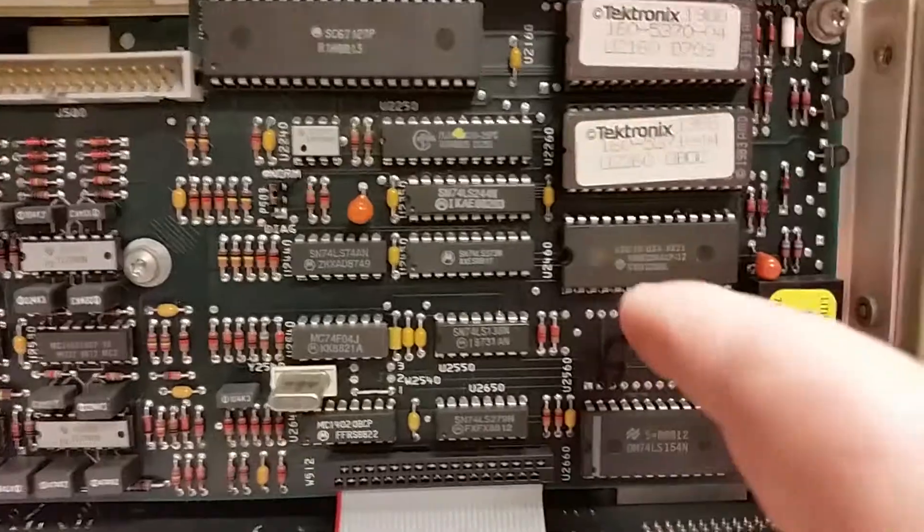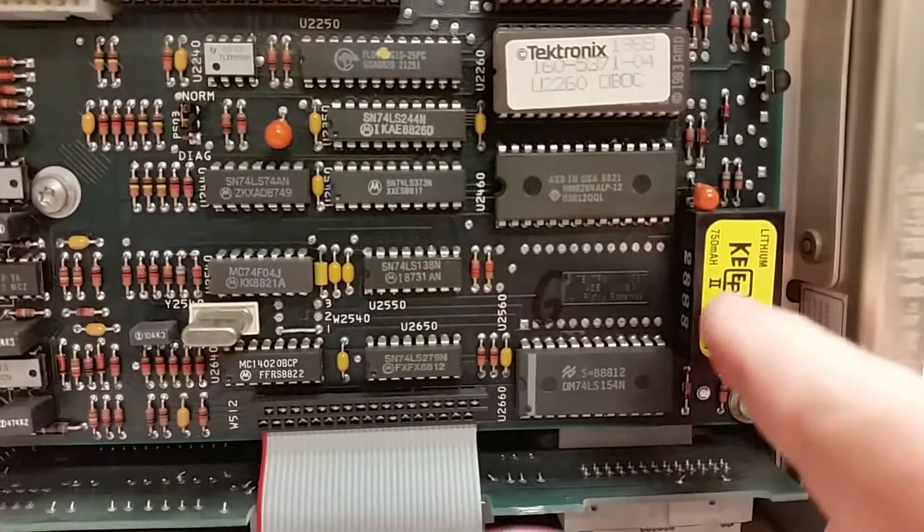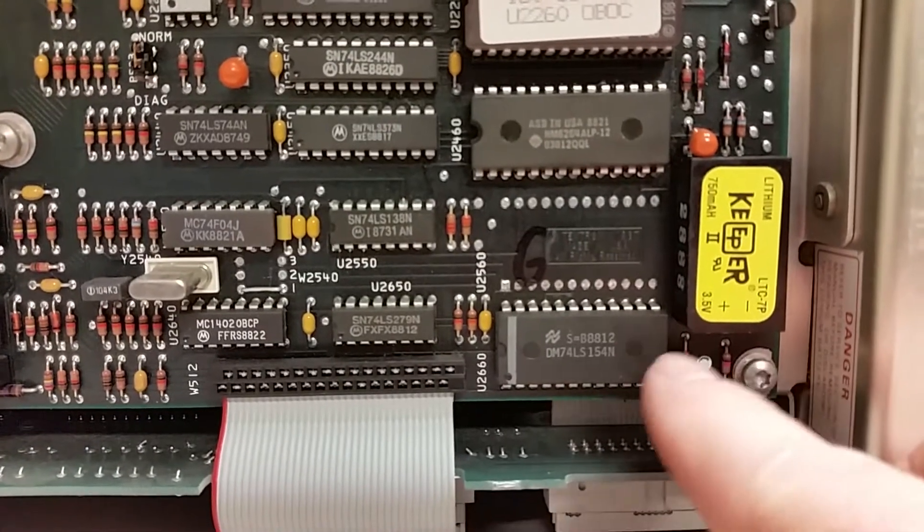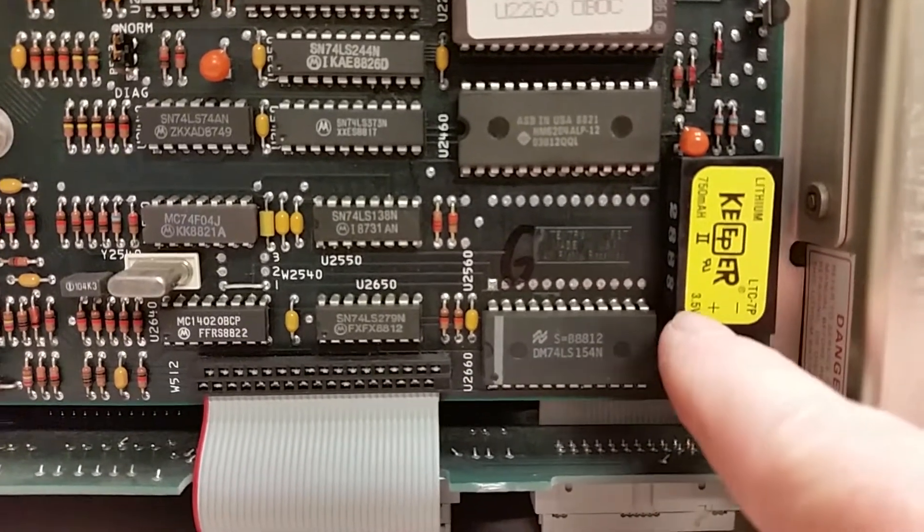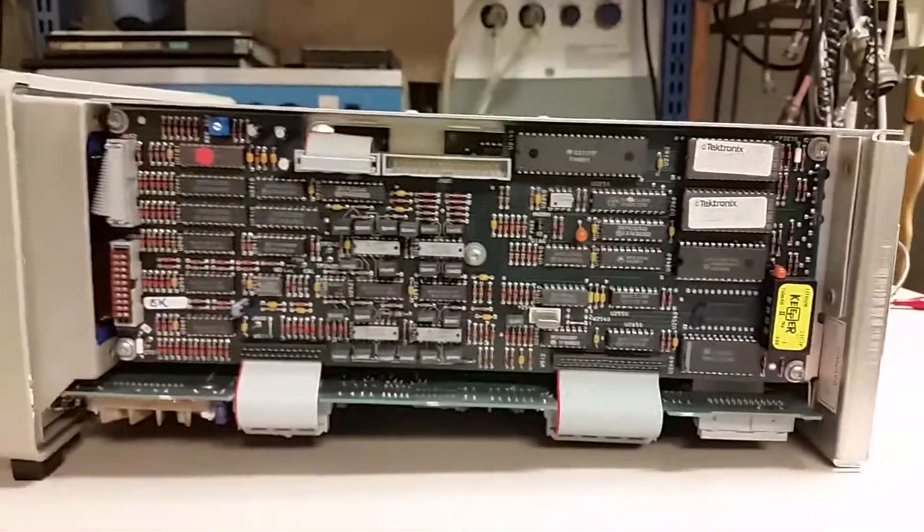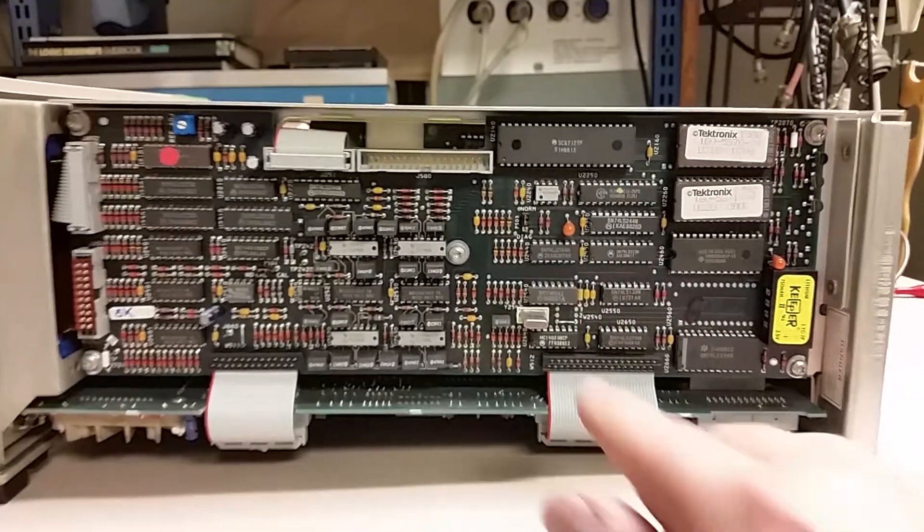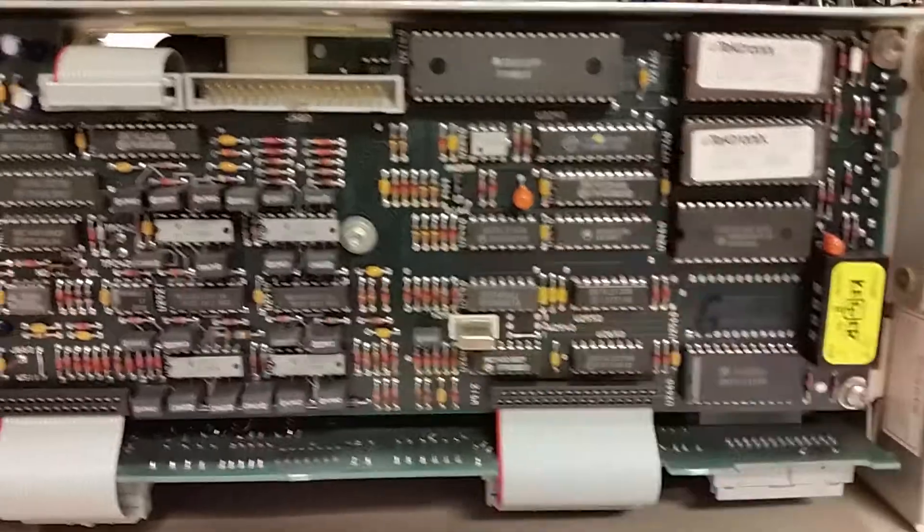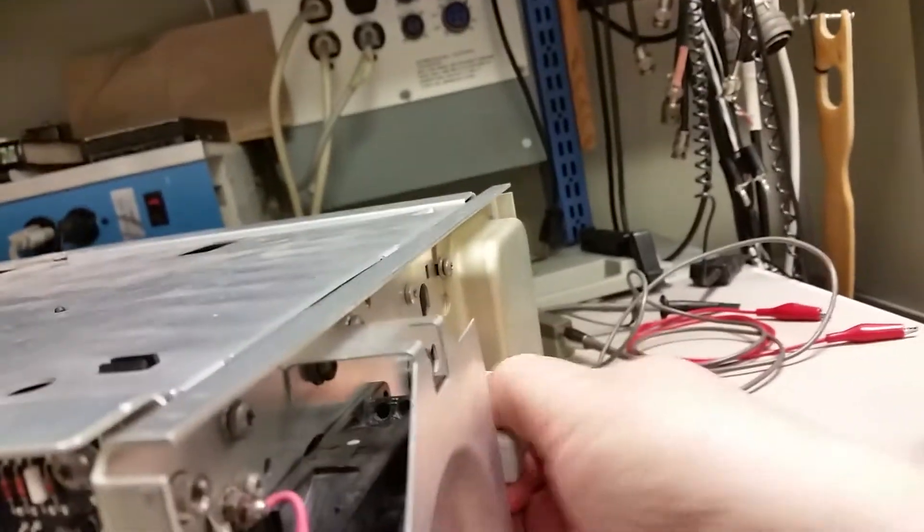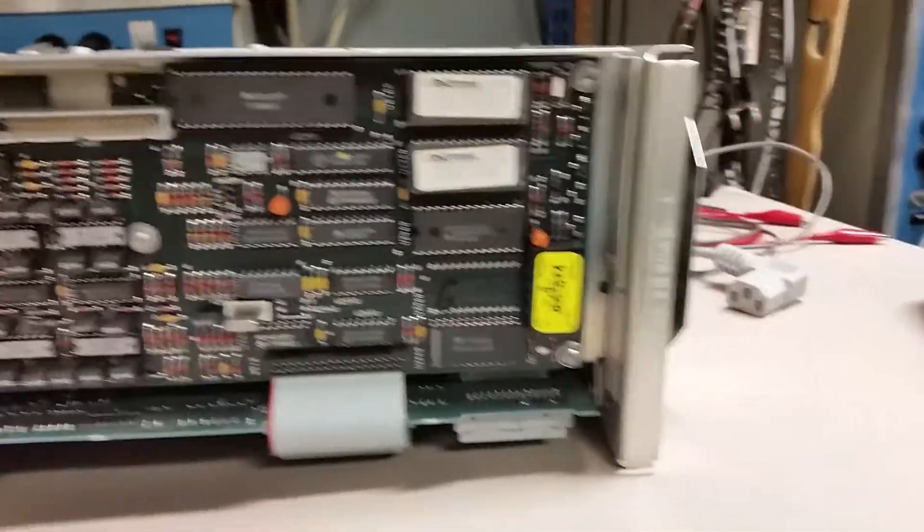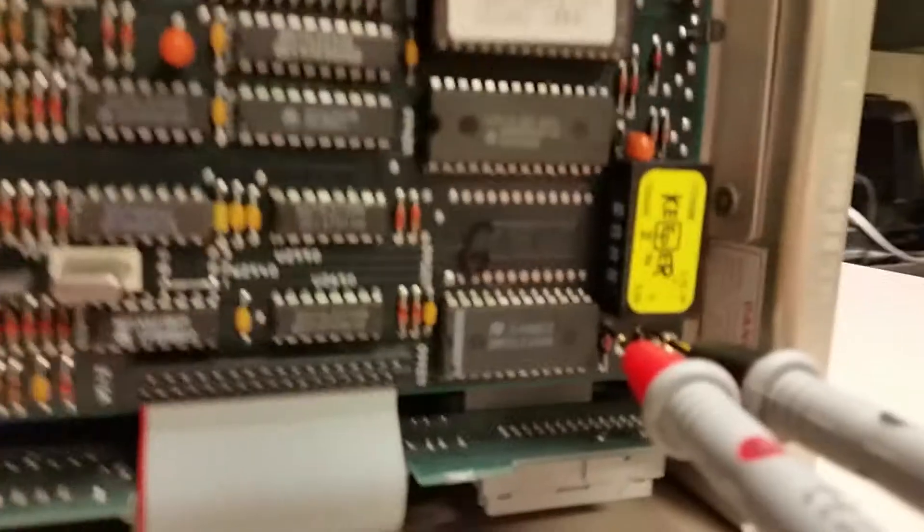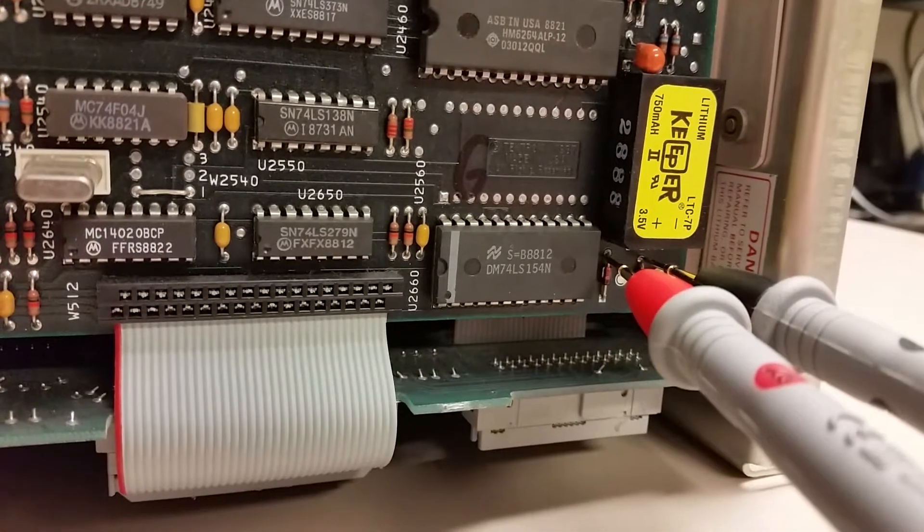and after I replaced it, I didn't know that that battery right there on the right I just pointed to is what actually holds the power on that. So if you pull that chip out, there's no power to hold the cal constants. So what I'm gonna do here is pull the power cord off to let you know it's unpowered, and then I'm gonna show you how to test that battery.